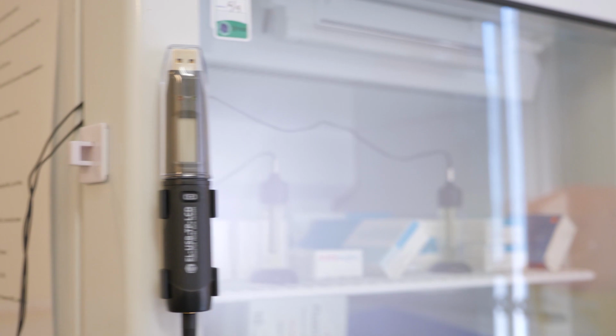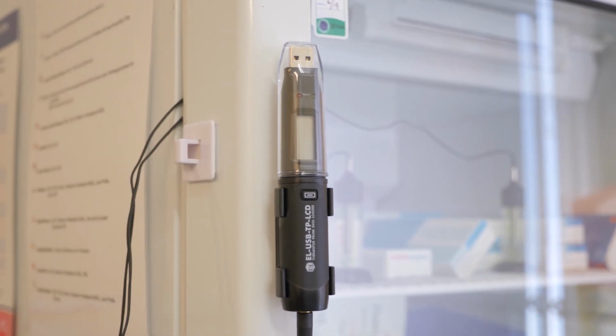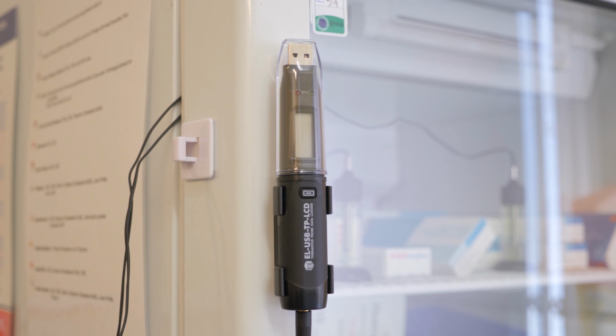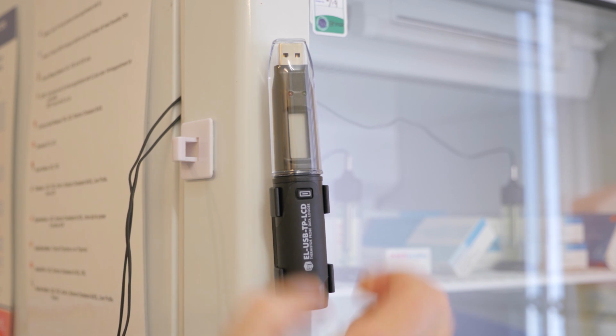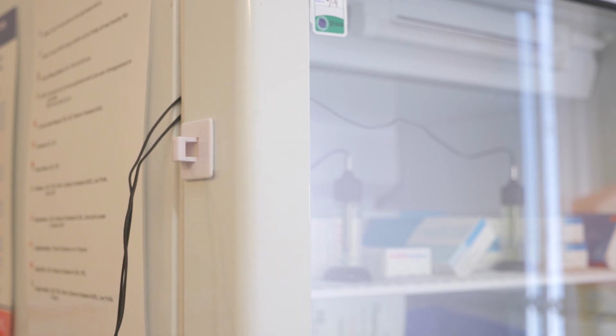You don't need to put the entire logger into the fridge or freezer. They have a magnetic clip so they can be fixed to the outside of the fridge or freezer, and just the glycol probe can go inside. Use the software to download your data at any time by detaching the logger from the probe. Leave your probe in the fridge or freezer so it doesn't have to reacclimatise later.